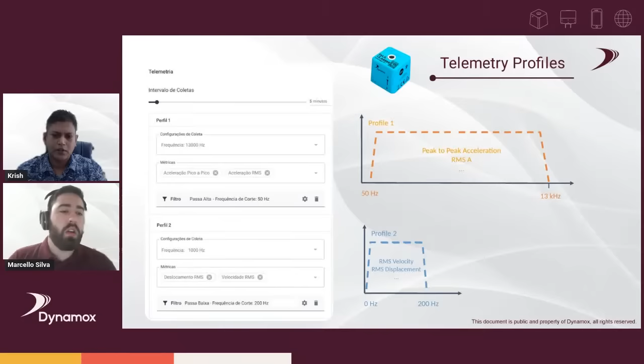So that's the main idea. For example, I would choose peak-to-peak acceleration and RMS acceleration. On the other hand, for the second profile, you can use a very low frequency range, for example from 0 up to 200, and this usually contemplates RMS velocity or even RMS displacement. That's the main point of using these telemetry profiles: you can define the metrics and the magnitudes, the frequency ranges are customized by the user, and of course you can define alerts for these as well. So you can define a high frequency alert and a low frequency one, so that when something goes up, you already know if it's low or high frequency related.